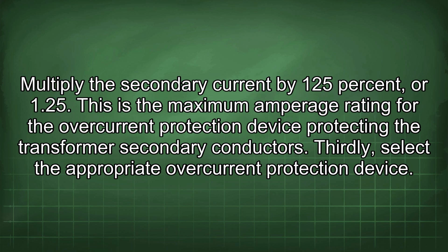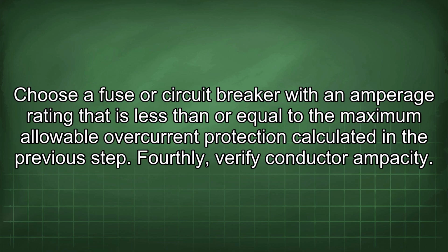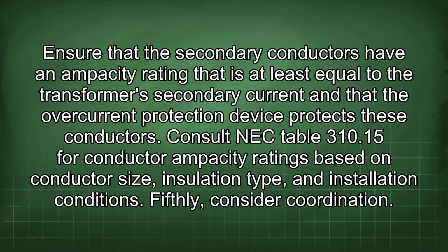Thirdly, select the appropriate overcurrent protection device. Choose a fuse or circuit breaker with an amperage rating that is less than or equal to the maximum allowable overcurrent protection calculated in the previous step. Fourthly, verify conductor ampacity. Ensure that the secondary conductors have an ampacity rating that is at least equal to the transformer's secondary current and that the overcurrent protection device protects these conductors. Consult NEC Table 310.15 for conductor ampacity ratings based on conductor size, insulation type, and installation conditions.